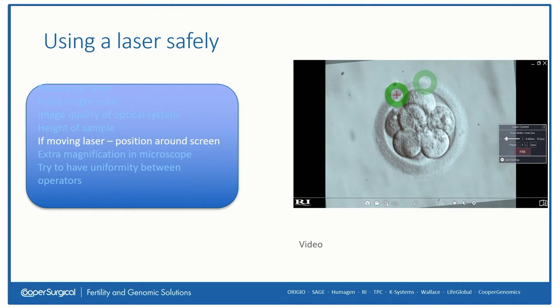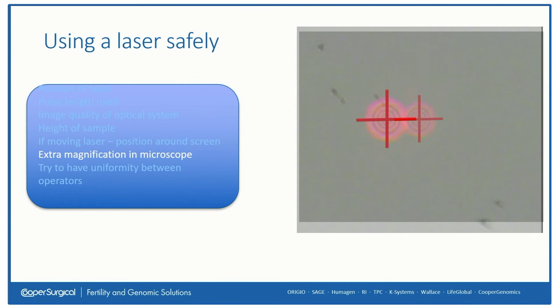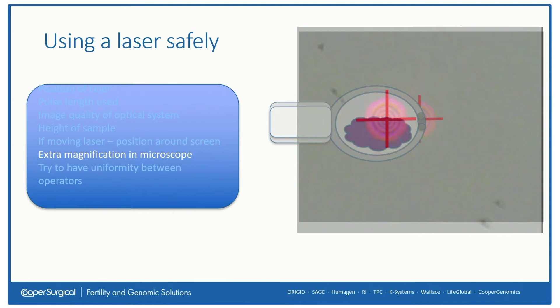If you have a 1.5x or other extra magnification lens in the microscope, be aware that using it may change the actual firing position of the laser. Here we see the target being checked against the center of the pilot laser on a 40x. But then after changing to the extra magnification from the microscope base, the actual position changes on the screen. And if you don't check if it's moved, you may end up positioning the embryo back at the original target site, which could then be disastrous for that embryo.